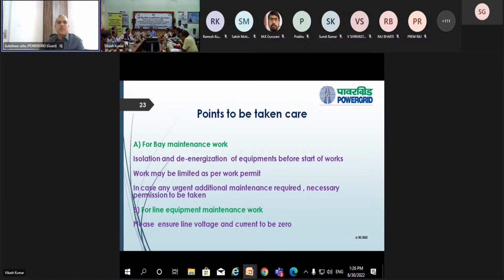For bay maintenance, please ensure the work area is isolated and de-energized before the start of work. Work may be limited as per the work permit. This is very important. Suppose breaker testing is planned, so we should limit it to the breaker testing during that permit. In case any urgent additional maintenance is required, permission has to be taken.